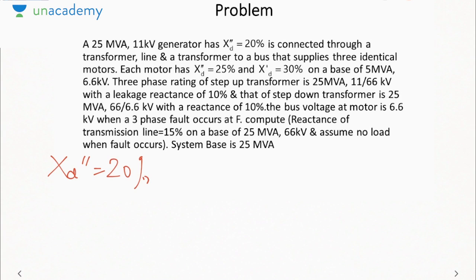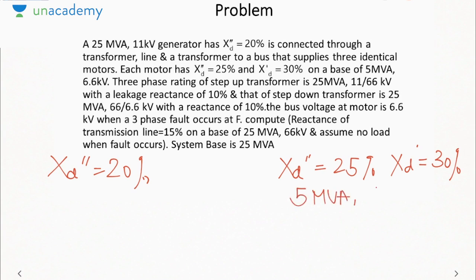Now it is connected through a transformer, a line and a transformer to a bus that supplies 3 identical motors. Each motor has X_d double dash of 25% and X_d dash of 30% on a base of 5 MVA, 6.6 kV. Okay, so the motor has a base of 5 MVA, 6.6 kV. The generator has a base of 25 MVA, 11 kV.